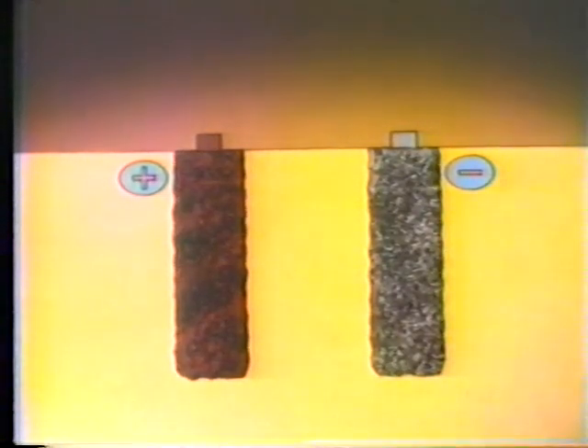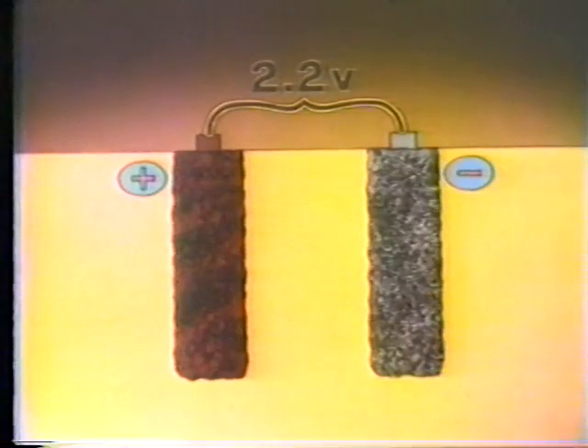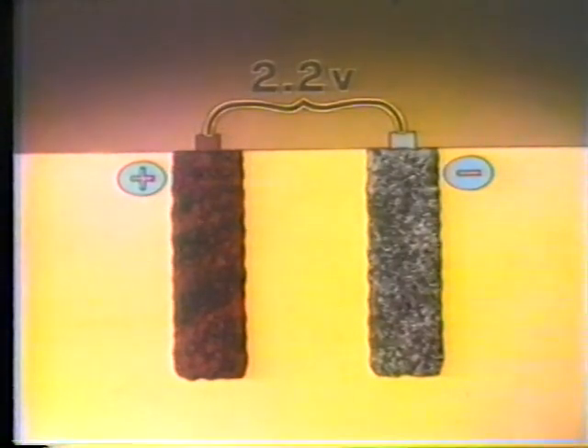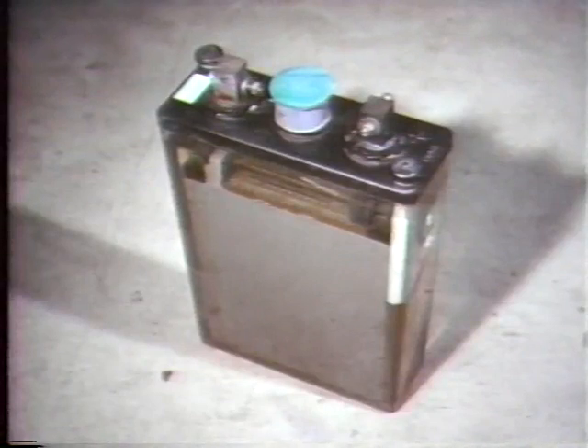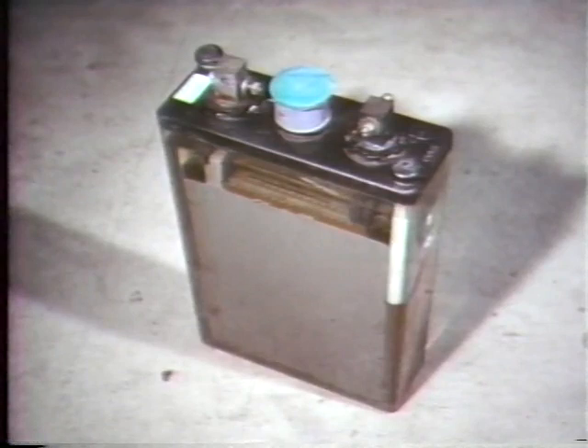Any lead-acid cell, regardless of its size, has a voltage of slightly over 2 volts when fully charged. For example, this cell has a voltage of 2.2 volts. But the size of a cell — or to be more precise, the surface area of its plates — does affect the cell's capacity, measured in ampere-hours.